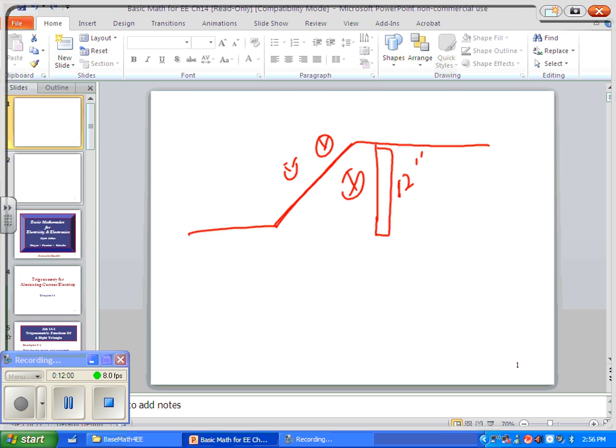And we stuck a stick in there and we realized, well, we need to be about 30 degrees. Except 30 is too much or too little, but we're going to say we need to go about 35 degrees to be able to get this conduit into the area we need to get into. So if we know that we've got to have about a 35 degree angle, that means we're going to bend this conduit up 35 degrees, and then back here, we're going to take it back down 35 to make it level.